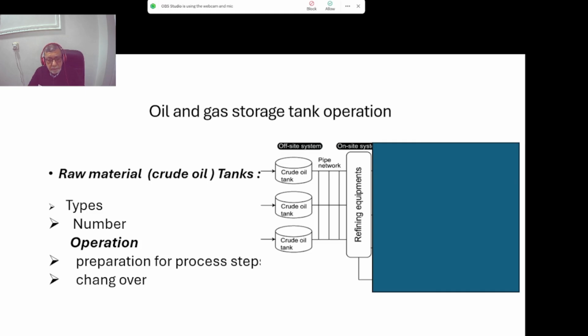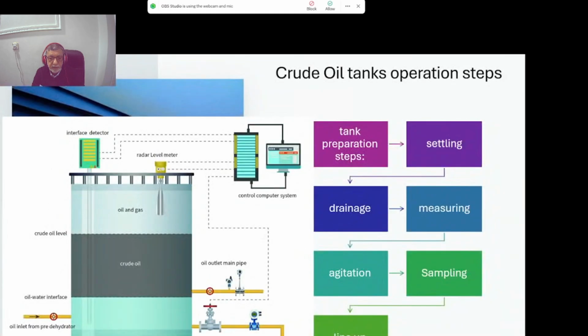When you change over from number 1 to number 2, the inlet valve for number 1 is closed and only the outlet is open. Then you have to open the outlet of number 2 because it is closed, and send the product to the CDU, and then close the outlet valve of number 1. The steps of operation, the tank preparation steps: first settling, after settling make drainage, after drainage measure the level of the tank, and not only the level, you also have to take the temperature at the same time, then agitation by mixer, take a sample, and then line up the tank. These are the steps of operation.